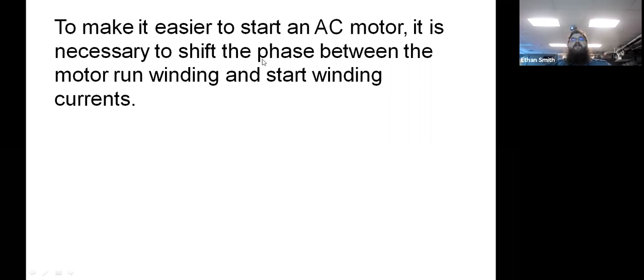So we've got a physical phase shift in just how the windings are positioned. And then we have an electrical phase shift that we can shift even more by making that electrical field delay on both its charge and discharge cycles. So the greater that phase shift, the higher starting torque. But if you go up too high, you phase shift it past 90 degrees, we can have a problem. So if you put too big of a capacitor on there and you phase shift that start winding more than 90 degrees out of phase with the rest of your motor, in some applications it'll actually start to fight your run winding and actually cause you more problems.